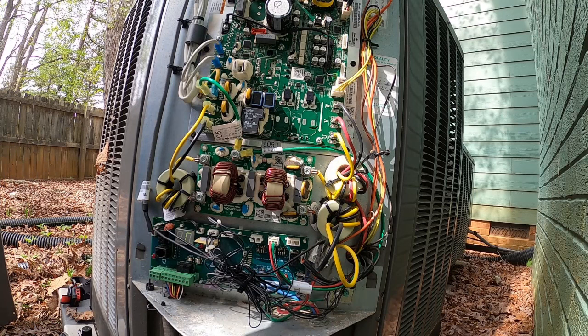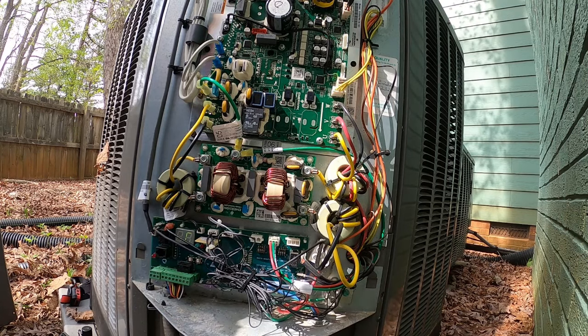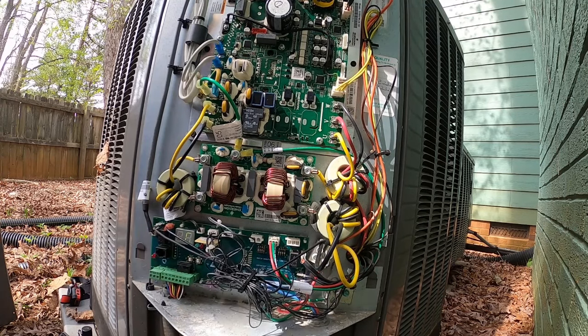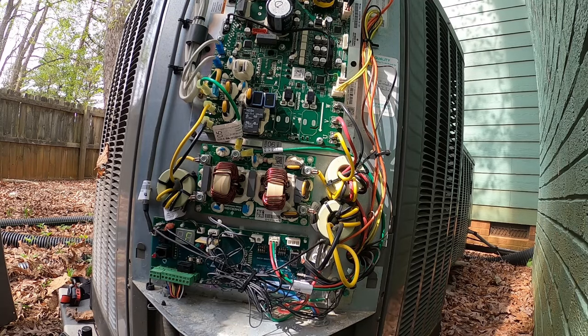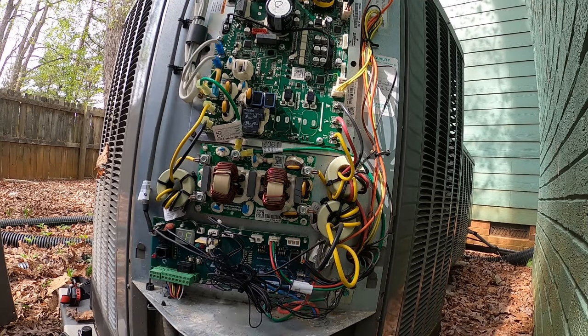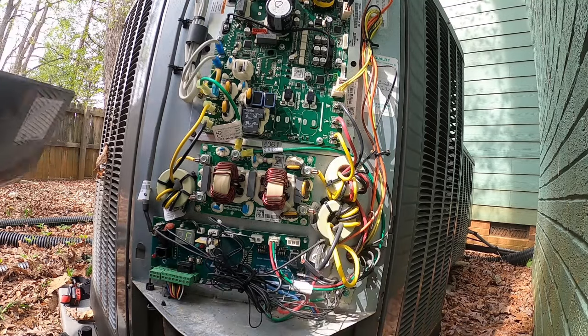we're running a 97 over a 203 with a 23 degree superheat and a 1 degree subcooling. And it's 72 degrees up there. The blower's been running for a little while, so there's some humidity and some heat in that evaporator right now. Little ants over here where I'm at. Gotta be careful. We'll let this thing run a little bit and see. There's no charging chart that I can see. Oh, there we go. Let's try that.